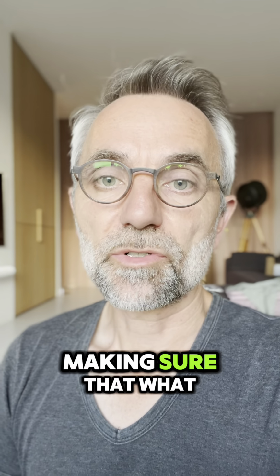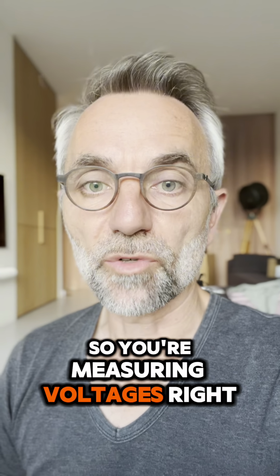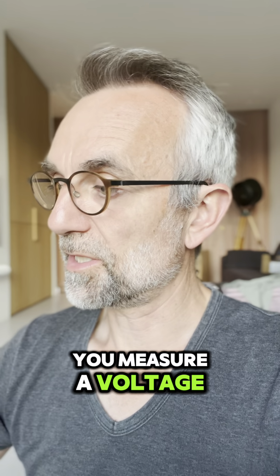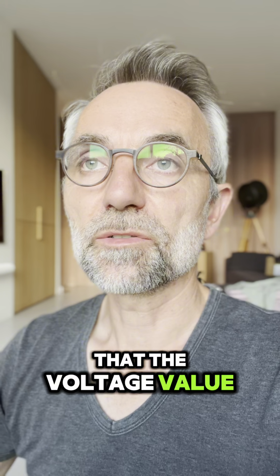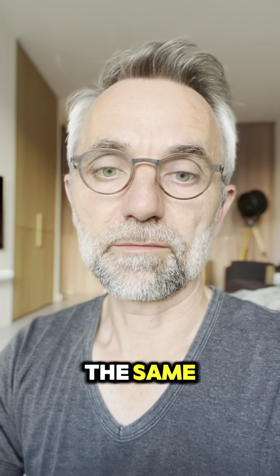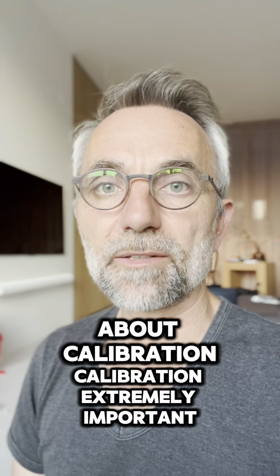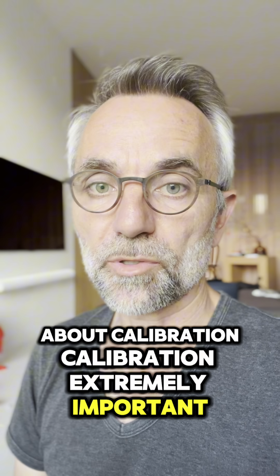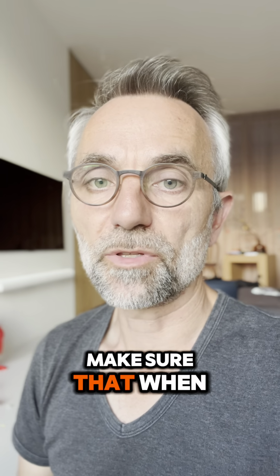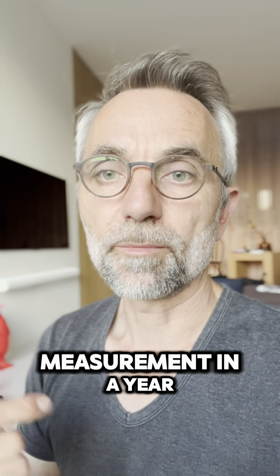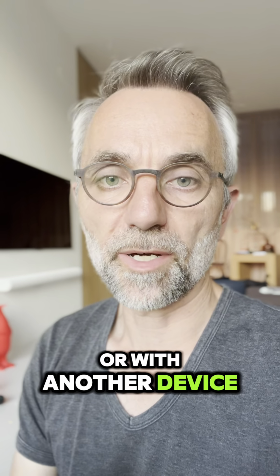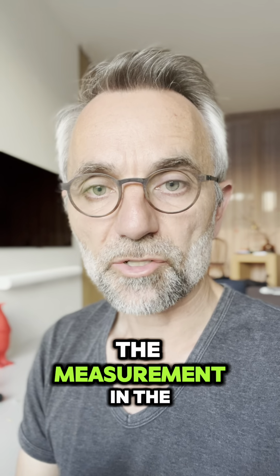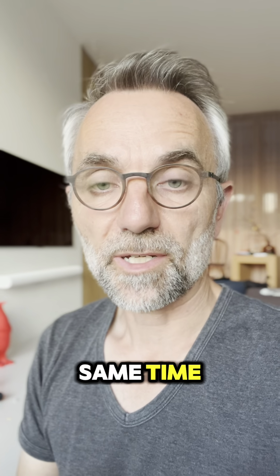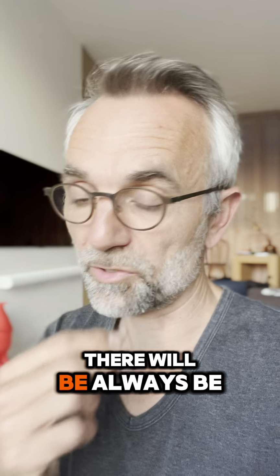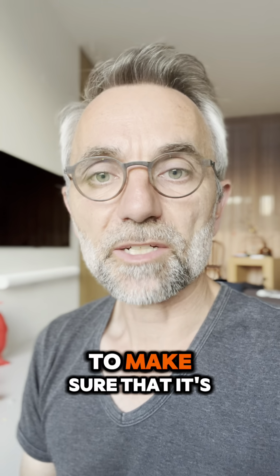Calibration is all about making sure that what you measure, so you're measuring voltages, right? You measure voltage for a specific sensor, that the voltage value is the same. So let's talk about calibration. Calibration, extremely important. Ultimately, we want to make sure that when you do a measurement now, or you do a measurement in a year from now, or with another device, that if they do the measurement in the same place at the same time, they will get the same reading. There will always be some difference, but basically you want to make sure that it's the same.